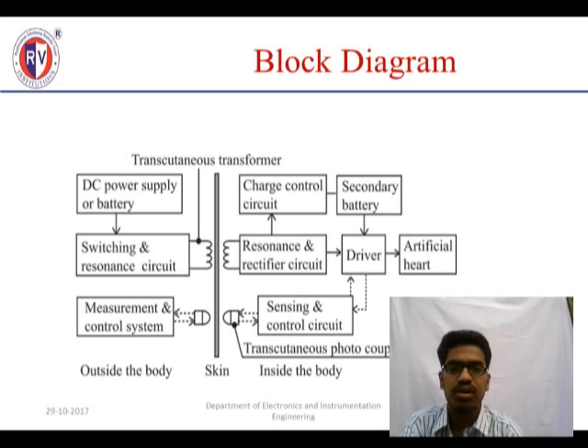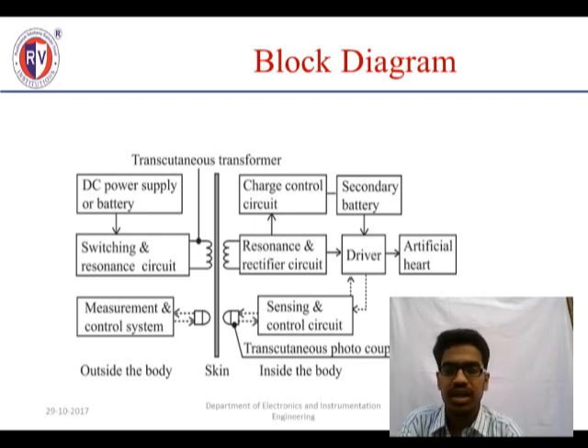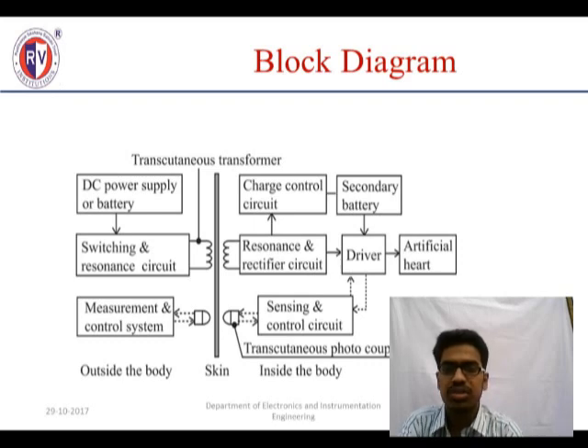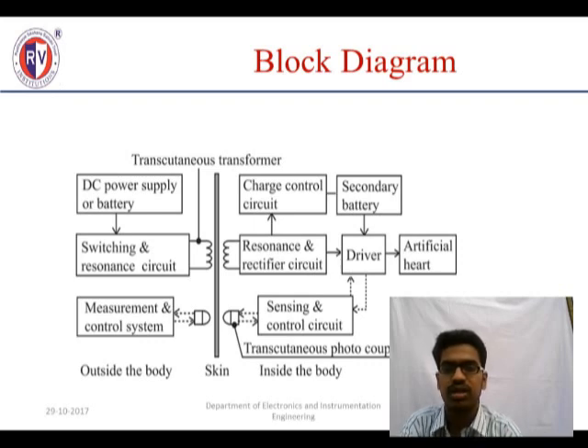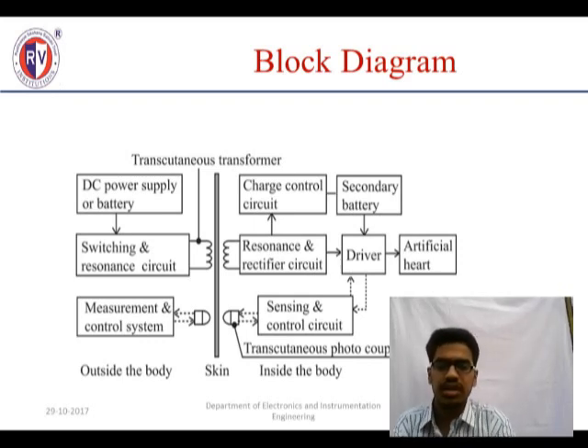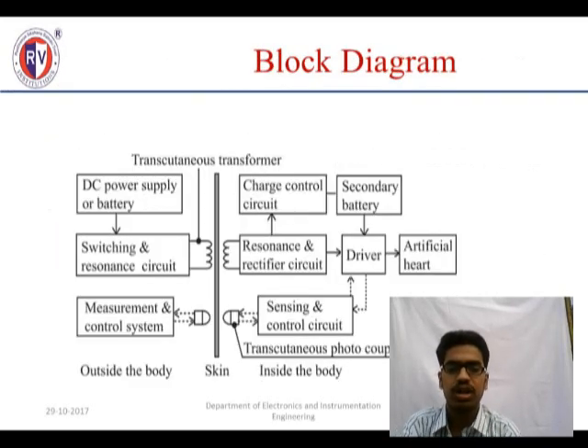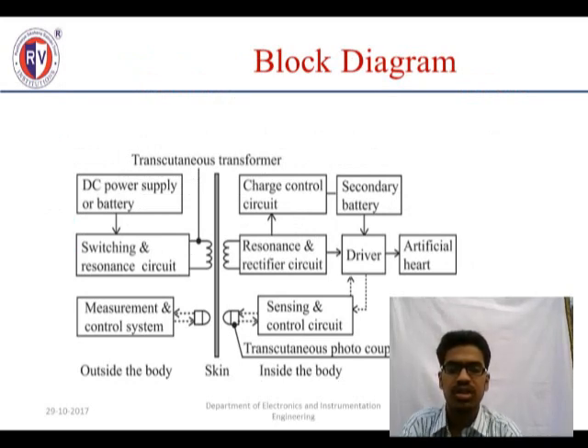Now we are looking at the block diagram of the artificial heart. The black line indicates the skin boundary. The external backpack consists of a DC power supply, battery, switching and resonating circuit used for switching the internal and outer transformer, and a measurement and control system that measures the artificial heart's beats and controls them as per the user's requirement.